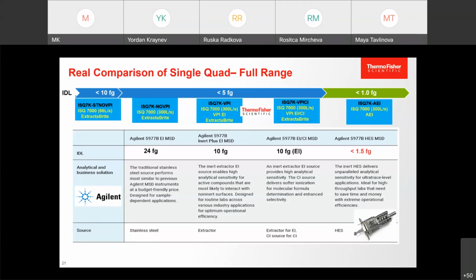If you look, with the small turbopump it is 10 femtograms. The rest, with the 300 liter pump, is 5 femtograms. Their extractor ion source is 10 femtograms. Extractor EI/CI is the same, 10 femtograms, and their high efficiency source, which you can see in the right down corner, is less than 1.5 femtogram, compared to our advanced electron ionization source, which is also less than 1 femtogram. That means in all parameters of limit of detection, we are even double better for the 300 liter pump, and for our top machine versus the Agilent top machine, we are 50% better than Agilent.